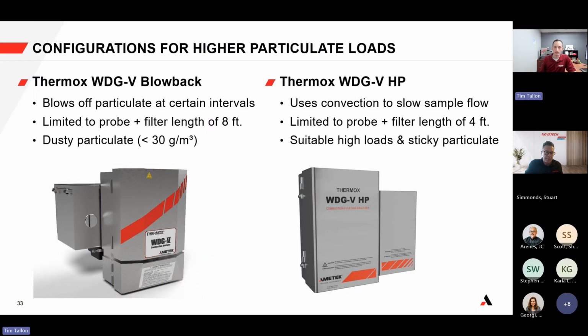So that's something we found, and it certainly is an advantage for handling some particulate without plugging up the analyzer or the filter. And as you mentioned, we also have bigger tubing within the internal analyzer tubing, which helps a lot in allowing it to whip right out. I think it's a really good point, because as you look around the industry, it's a bit of a unique feature of the Thermox that it does it that way, and that's the reason why we have a lot less filters on the end of our regular probes.